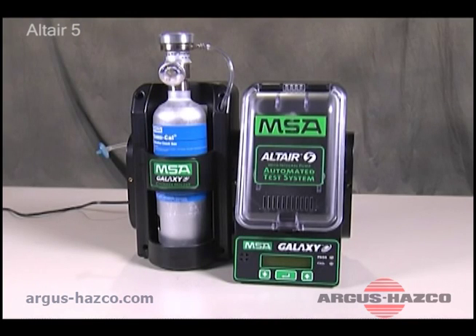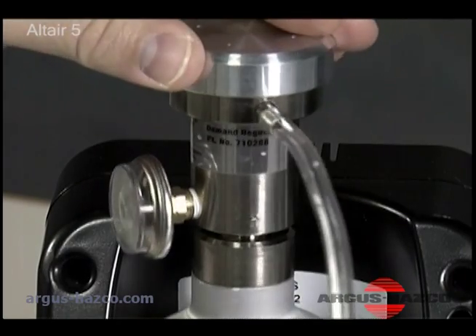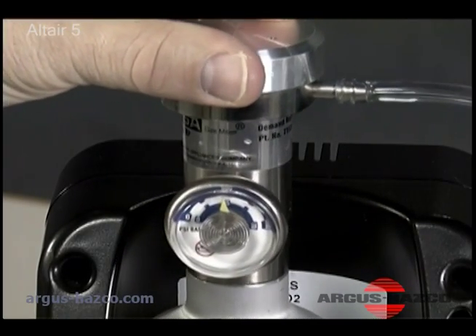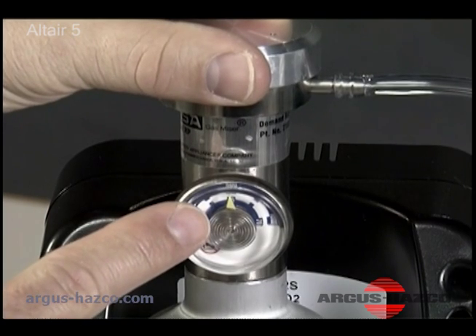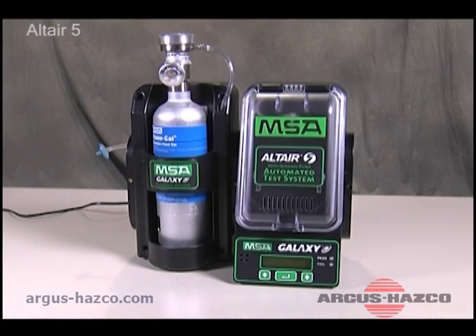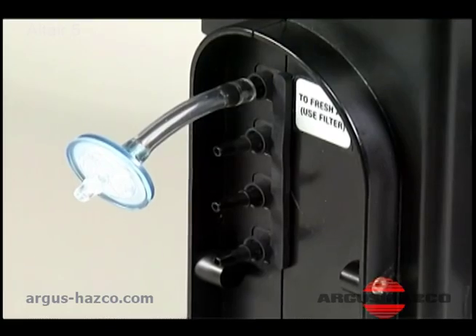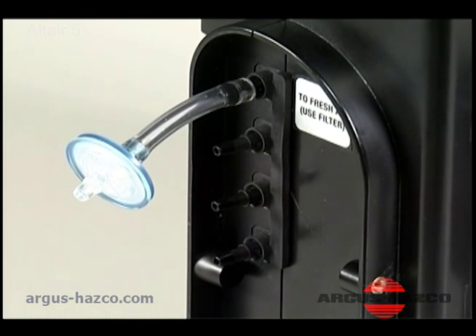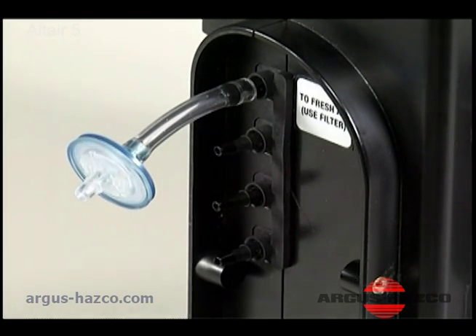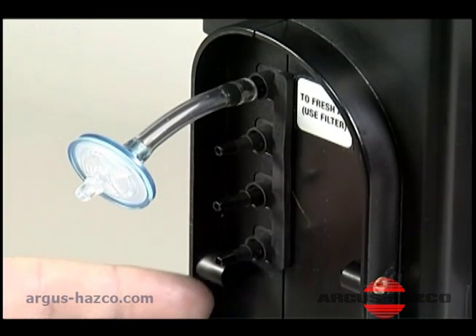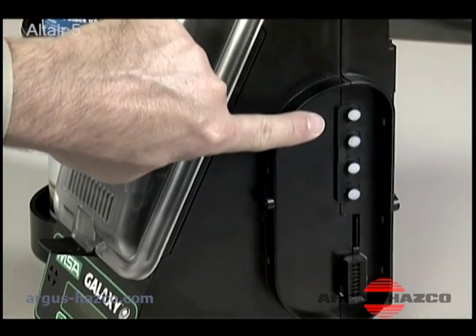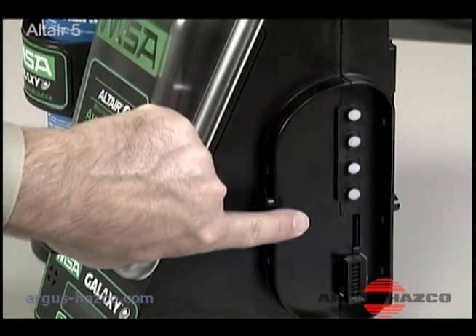Before attaching the cylinder holder, make sure the demand regulator is installed properly and that the gas tube is connected. Also, make sure that the cylinder has enough gas. Place the test stand on a stable, flat surface. There are 4 barbed fittings for fresh air or test gas cylinder connection on the left side of the unit and 4 inlet ports for attaching multiple units on the right.